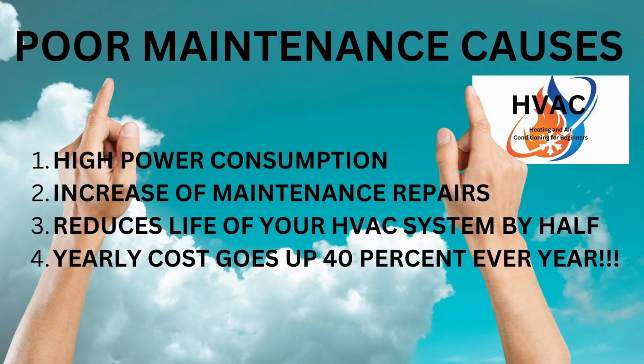And when we're talking about power consumption, I'm talking about wattage. That means an increase in watts, an increase in amperage. So, you know, Ohm's law states you increase more if the unit runs more. You're increasing your amps because it's not running at capacity, and that means that motor has to work harder, which increases your wattage and your power readings. That's why your electric bill goes up. It's because you're putting pressure on a motor and it's working harder than it should due to lack of maintenance.